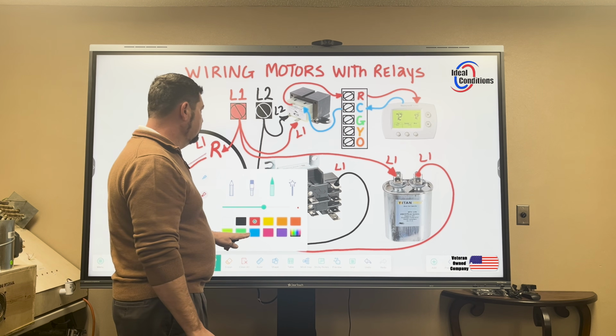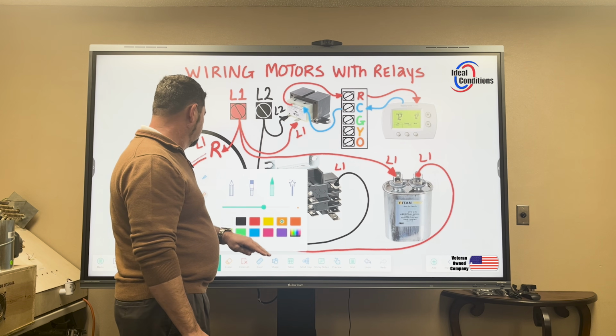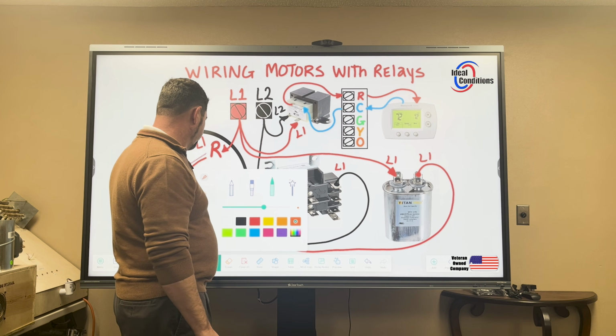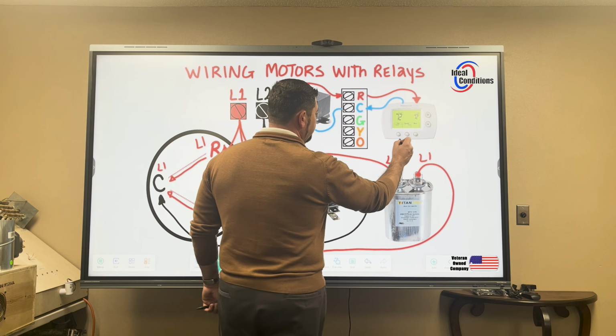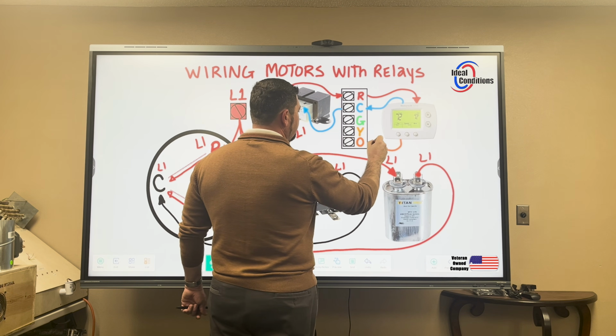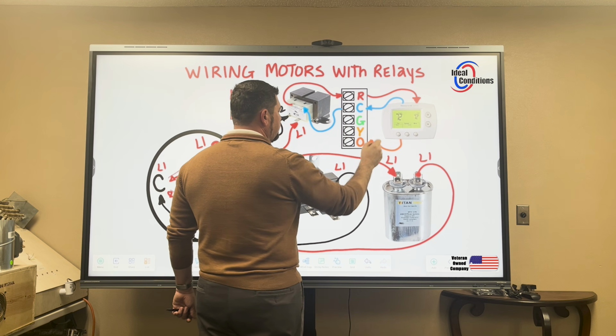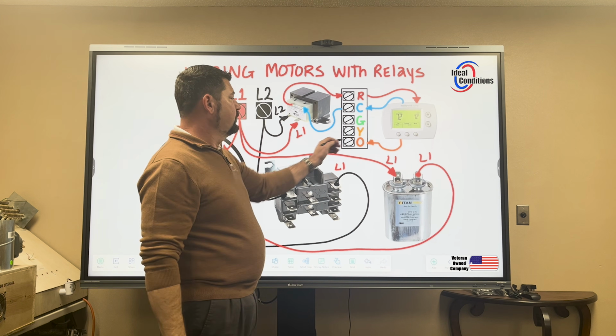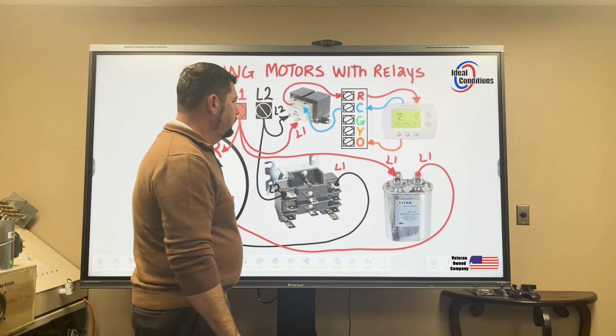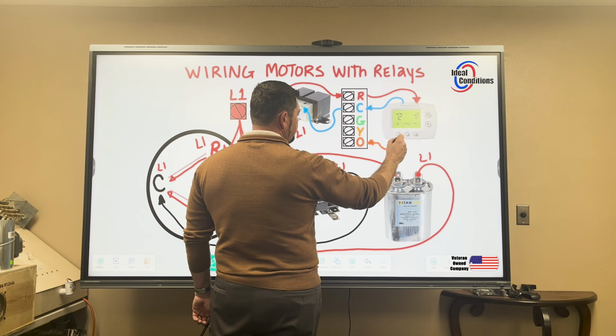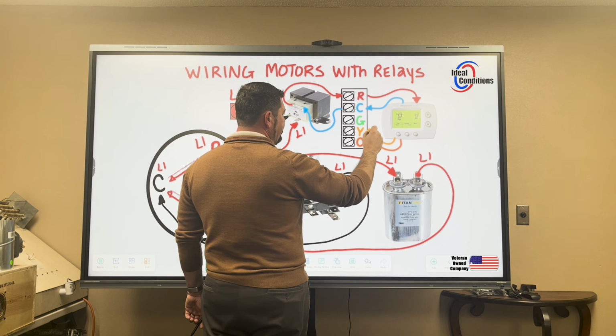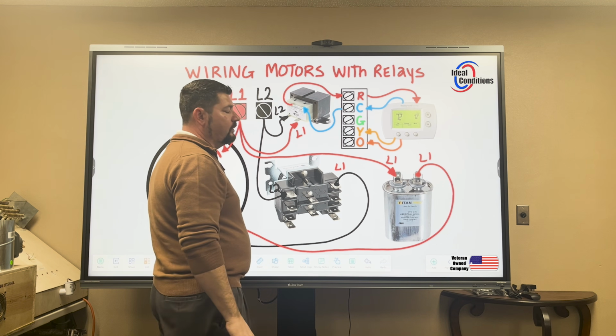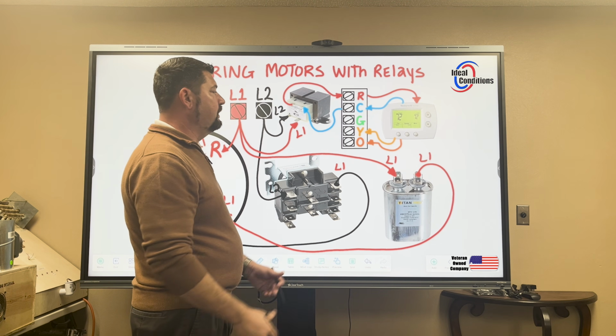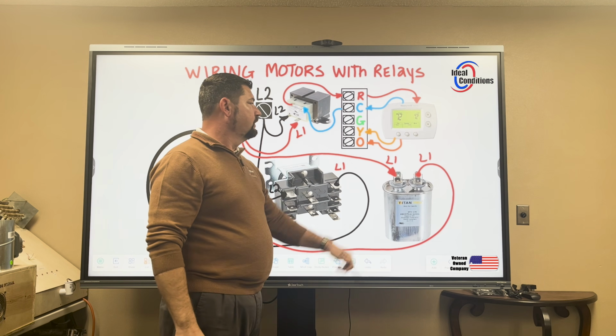We're going to go ahead and say we need Y and orange next. So we're going to go ahead and do O. Okay, thermostat puts power out on O for a cooling call. It puts power out on Y for a heating call, but it also brings on the condenser. So if it's not a heat pump, you won't have the O, you'll just have the Y.